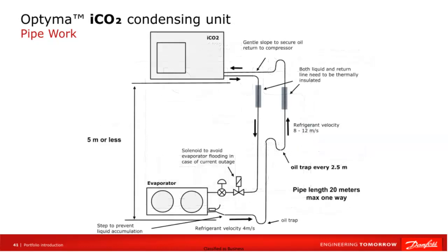In this case, we have a different configuration where the condensing unit is located at the top and the evaporator is at the bottom. It is worth paying attention to several important aspects. In such an installation, it's recommended to use an oil trap in the suction pipeline every 2.5 meters. Sufficient diameter of the suction pipe is necessary to ensure proper flow velocity in the range of 8 to 12 meters per second. Thanks to these solutions, we ensure effective and reliable operation of the installation, even when the unit is placed at the top and the evaporator at the bottom.